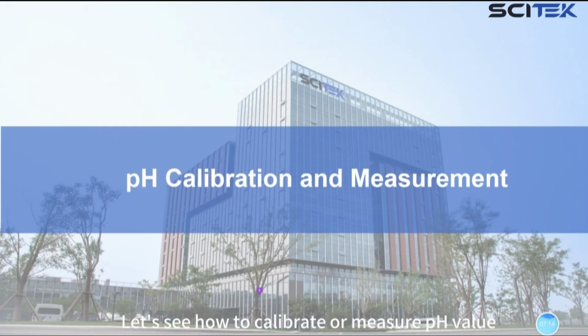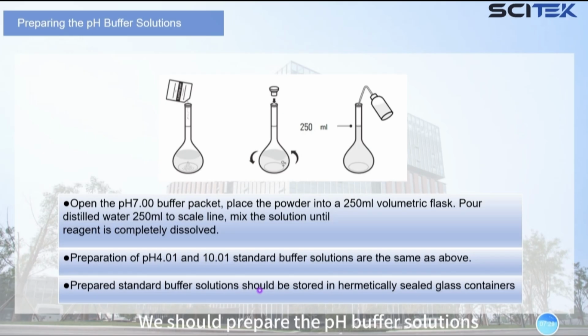Let's see how to calibrate or measure the pH value. We should calibrate when first using or replacing the pH electrode. Before calibration, we should prepare the pH buffer solutions. This is the process. Open the buffer sachet. Place the powder into a 250 ml volumetric flask. Pour distilled water to the 250 ml scale line. Mix the solution until the reagent is completely dissolved.